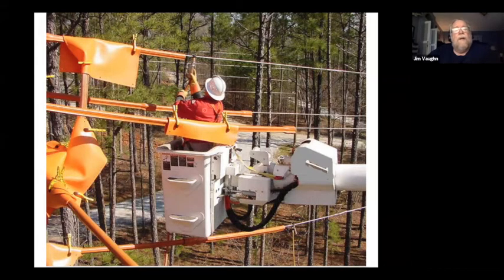Now, here's what I want to tell you. This looks good. For some people, it probably looks like it's extra, but it is actually not enough. And here's why. This is the exposed conductor. The end part of this hose is not considered insulating for about the first 6 inches or so, because there is a little bit of tracking that takes place on the contact portion of the hose. But here's the problem. Most linemen think that if they can't reach that from where they work, they're safe. But that's not what the rules say.